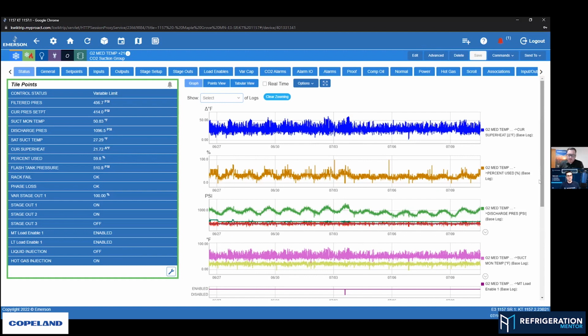For a long time, as most good technicians know, stable suction control has been the heart of a CO2 refrigeration system. Condensers have always been important in the system, obviously they have a job to do, but the gas cooler is very close to being an equal partner in suction control, in my mind, on a CO2 system. If that gas cooler isn't running right, the whole system is upset, and you'll see the high pressure valves and bypass valves fighting the gas cooler as we surge for subcooling and things like that. So those are probably my main 4 or 5 points I'm going to look at first, just to try to get a few days of data.